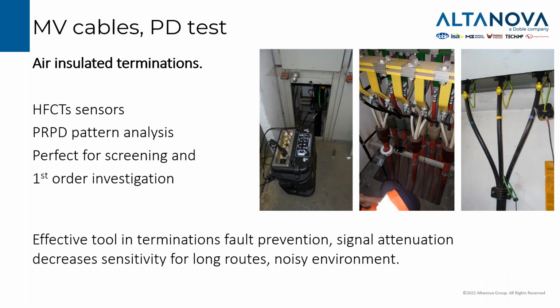Let's see now the typical test that we can have in medium voltage. So if we have an air insulated termination, we will use a high frequency current transformer placed on the ground leads of the termination or directly around the cable. For example, you have the HFCT around the whole cable in the picture in the middle, while you have the HFCT on the ground lead of the termination in the picture on the right. It can be used as a first order investigation, so we can have in some lucky cases the PD localization, or we can just have the information that the system is PD affected.